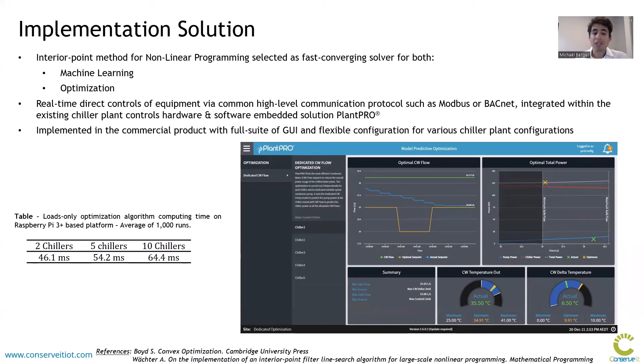The solution for the optimization uses an interior point method for nonlinear programming, which for the number of variables handled here converges very fast with relatively low computing power requirements. This was used for both the machine learning — finding the minimum error and best coefficients for the models — and for the optimization problem to find the best set points. As shown in the table on the bottom left, running cases with two, five, and ten chillers, the optimization always completes in below 70 milliseconds, which is more than sufficient for controls that operate in the seconds range.